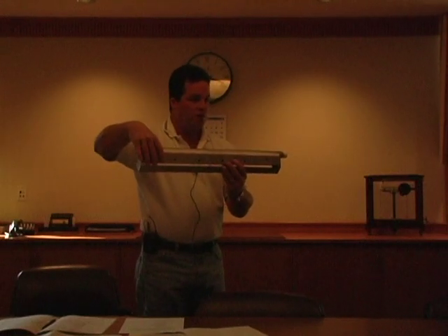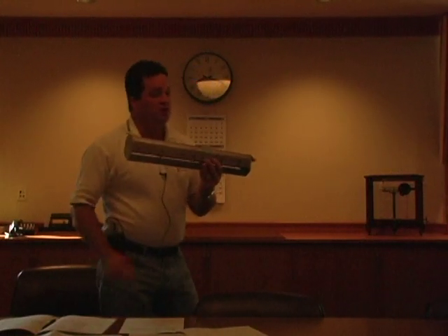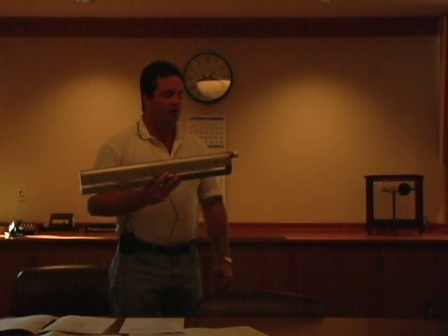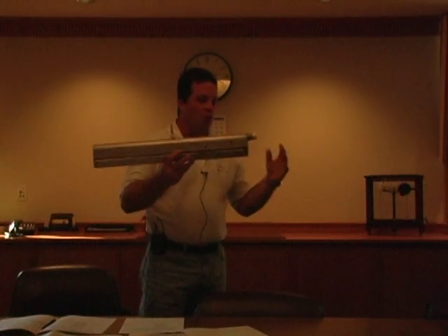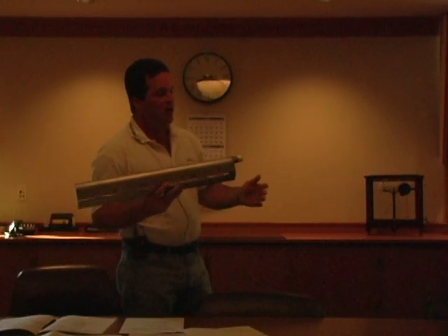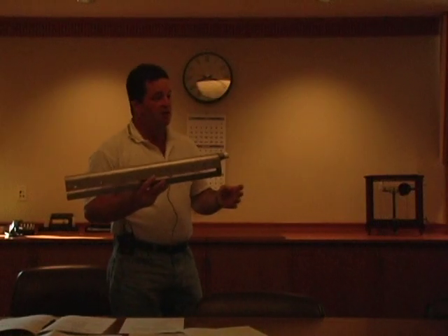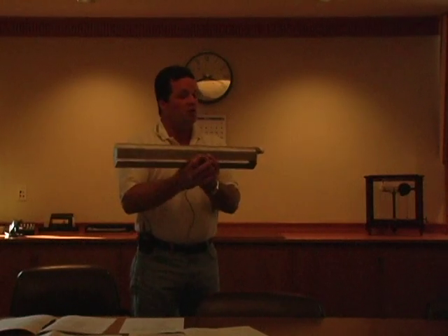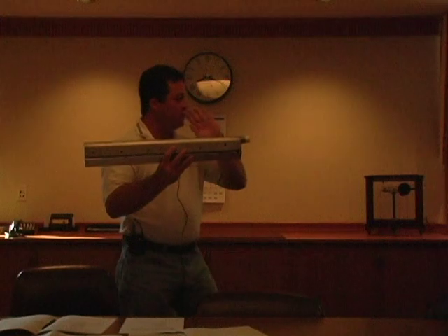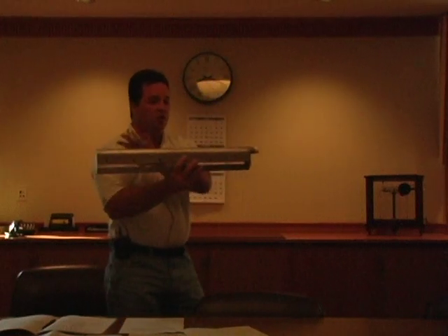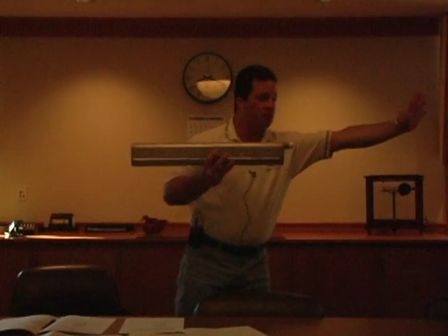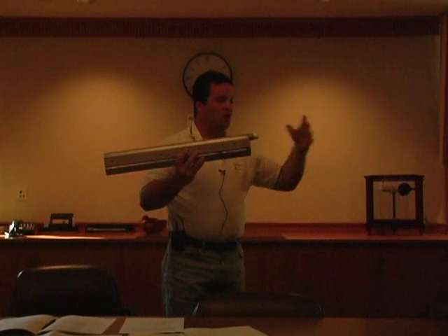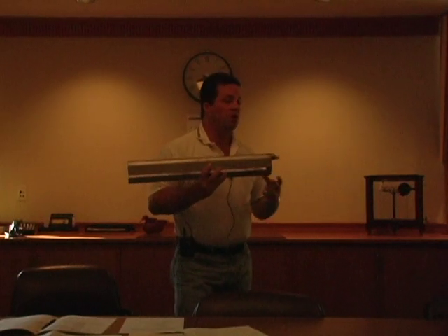Operational range on these diffusers is from 4 or 5 CFM to 40 CFM per diffuser. So you've got a wide range of airflows that you can run through here. We recommend that you run it at least somewhere around 10. 10 seems to be a good number for equal distribution through the diffuser. So basically, with this header line going down a channel, we want to make sure that we've got equal distribution in aerating throughout the channel and not have any dead spots. Dead spots would actually incur settling in that particular area, and that's what we're trying to avoid.